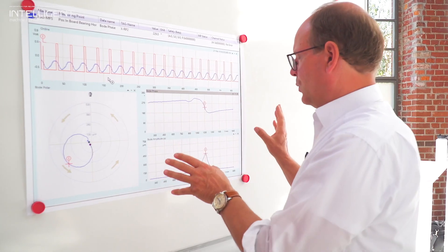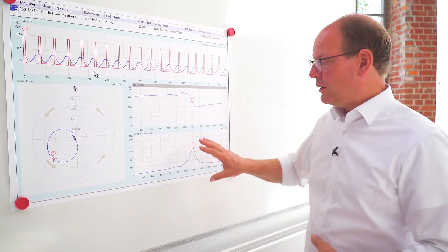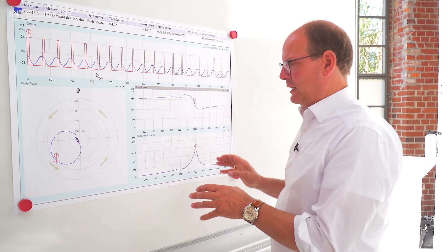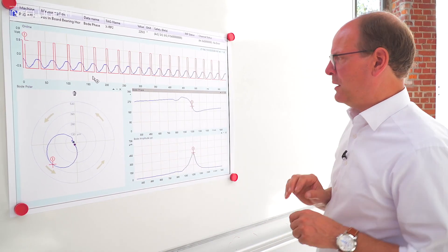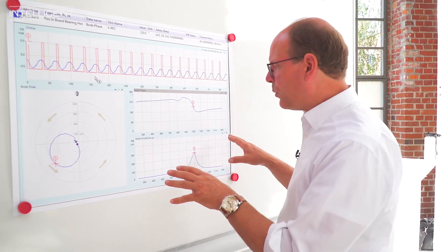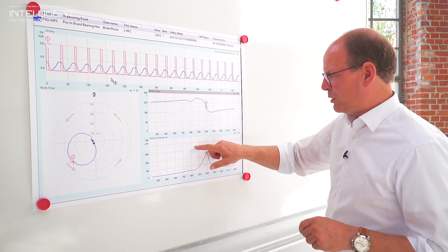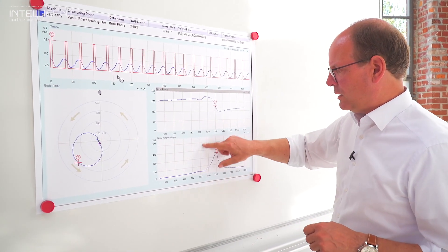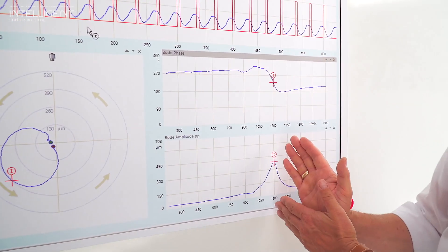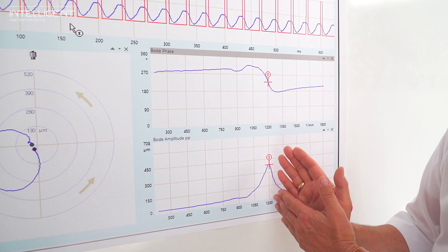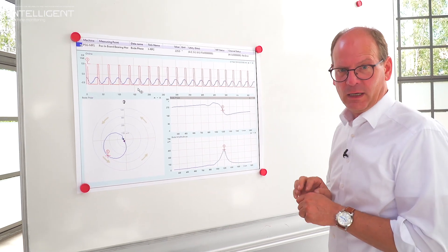What we also can do is that we use a set point multiplier here for this critical speed. That means if we have a safety system, if we have a machine protection system, and we normally have a protection limit, then we can here use a set point multiplier which will use a different protection limit exactly during this critical speed when the machine is running up, to avoid alarms for example.